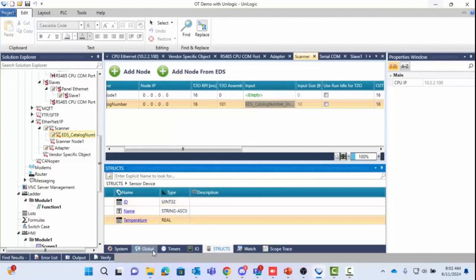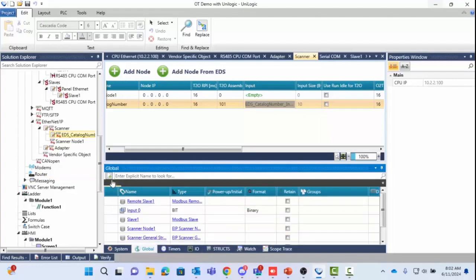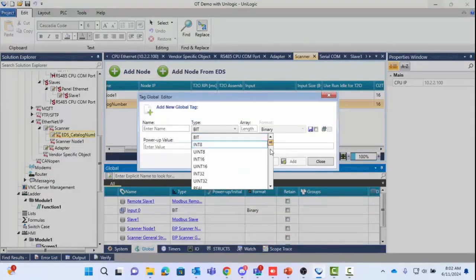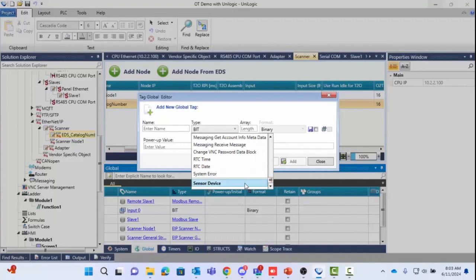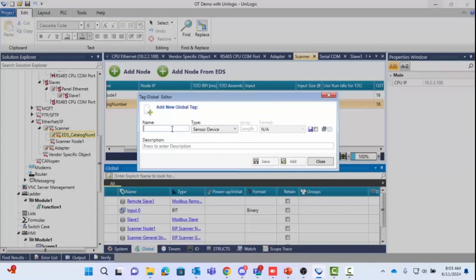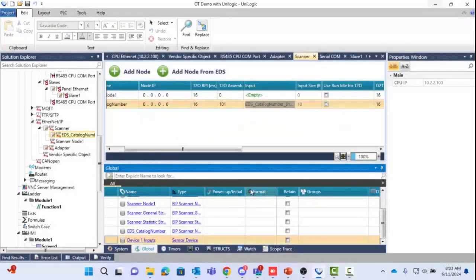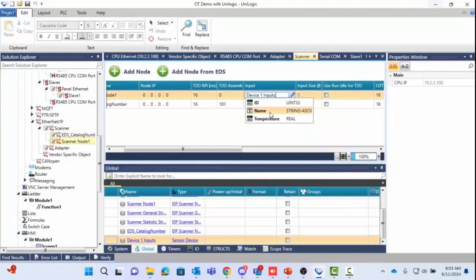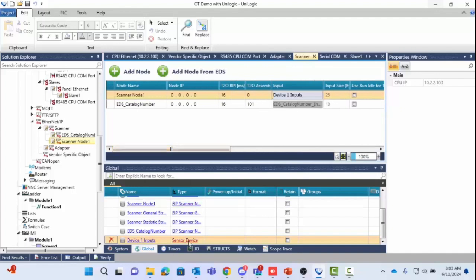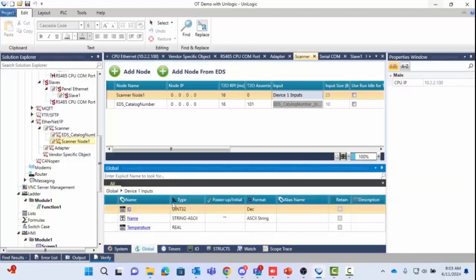To instantiate the struct, go to Global tags and create a variable of that struct type. Scroll to find the 'Sensor Device' struct we created, name it 'Device 1 Inputs', and then in the Ethernet/IP settings, set that tag as the inputs — the whole struct gets populated with data read from the adapter device.